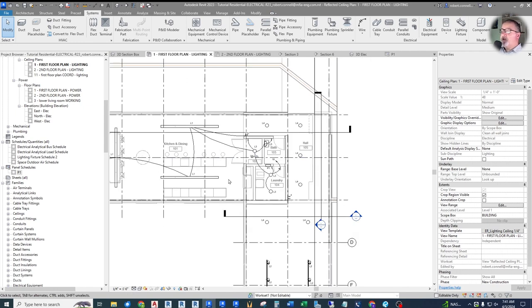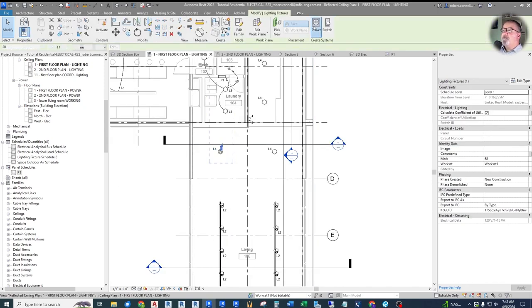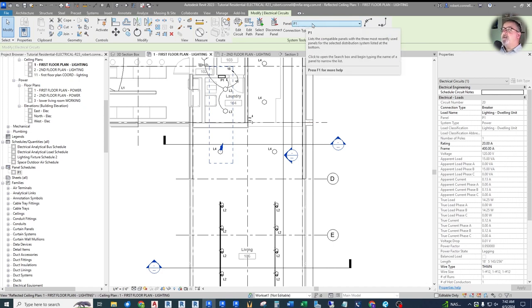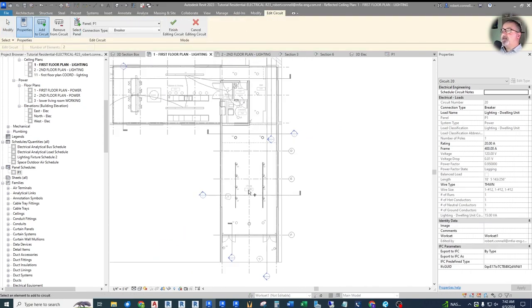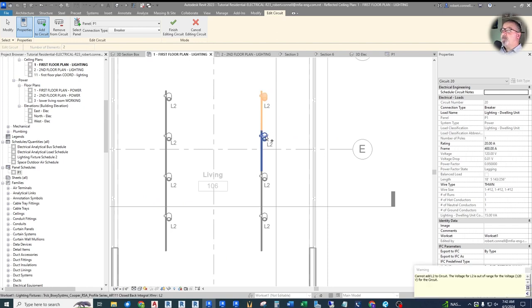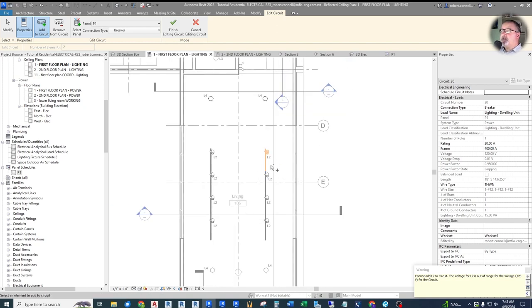Now let's circuit the rest of the rooms — grab one fixture, hit the power button, and edit the circuit to add other lights. However, when I try to add an L2 track light, I get a warning: 'Cannot add L2 to the circuit — the voltage for L2 is out of range for the 120-volt circuit.' You'll run into this when a fixture is set to the wrong voltage. On commercial buildings, lights may be 277-volt on 480-volt systems, so Revit prevents connecting the wrong voltage fixture.